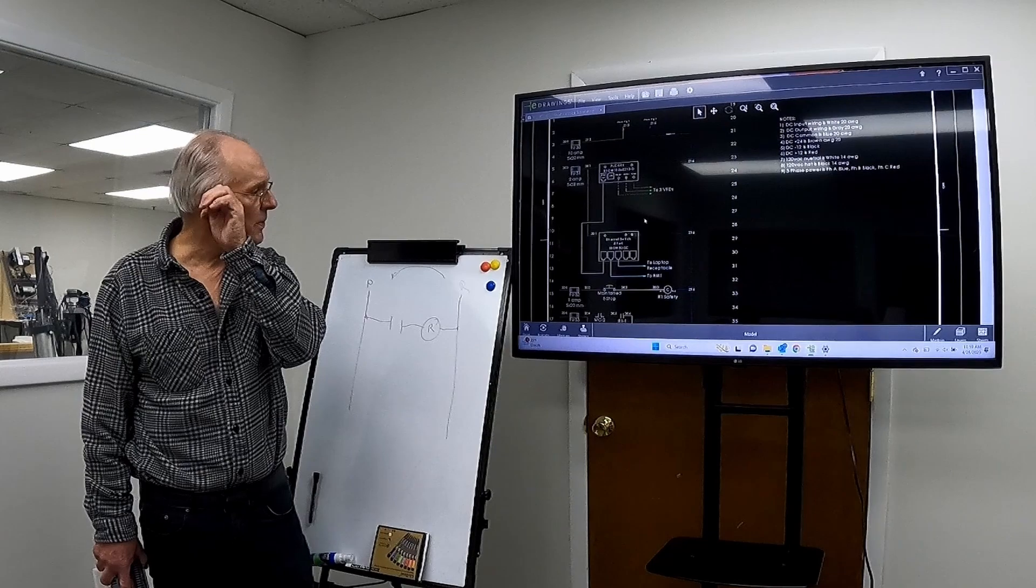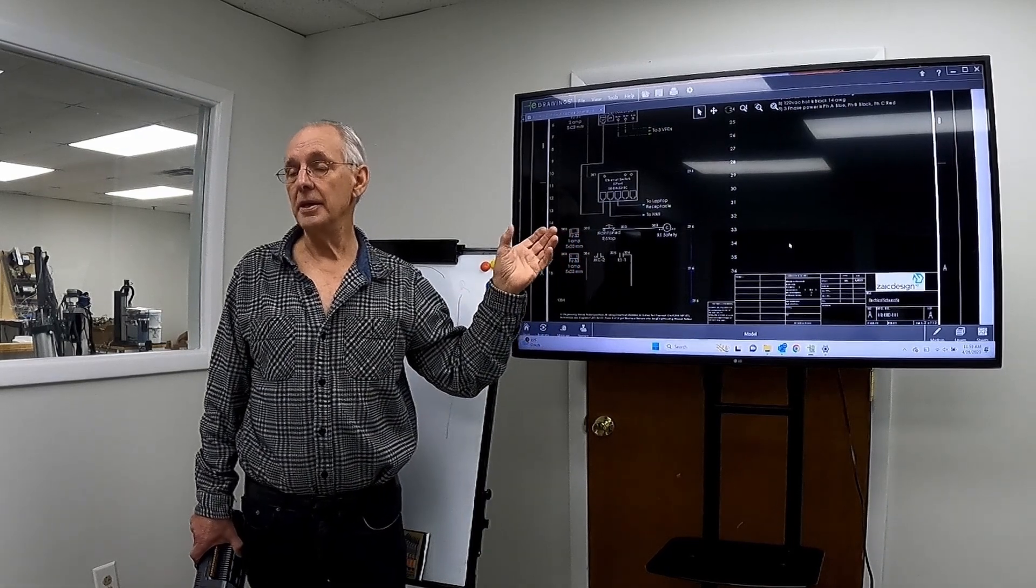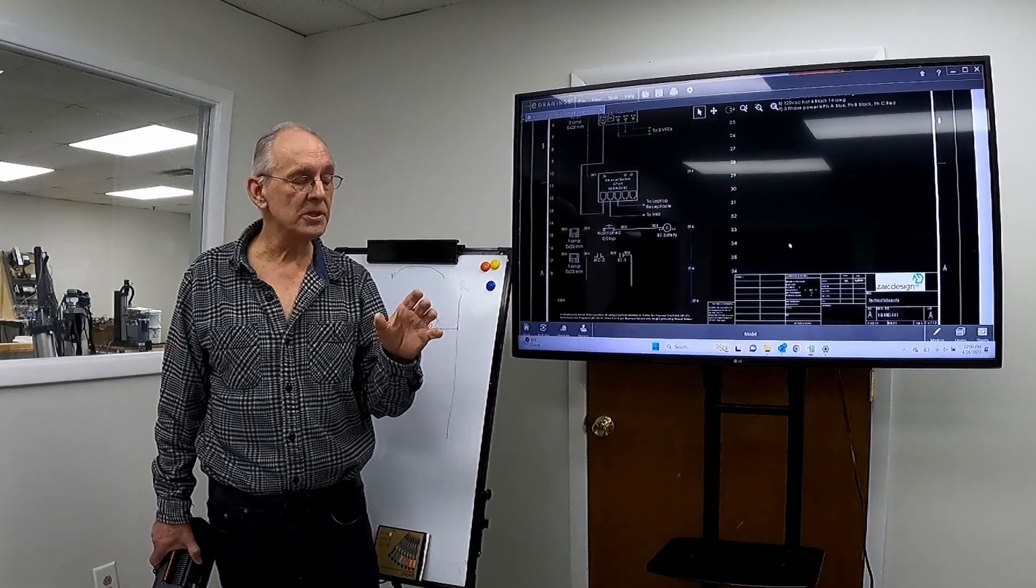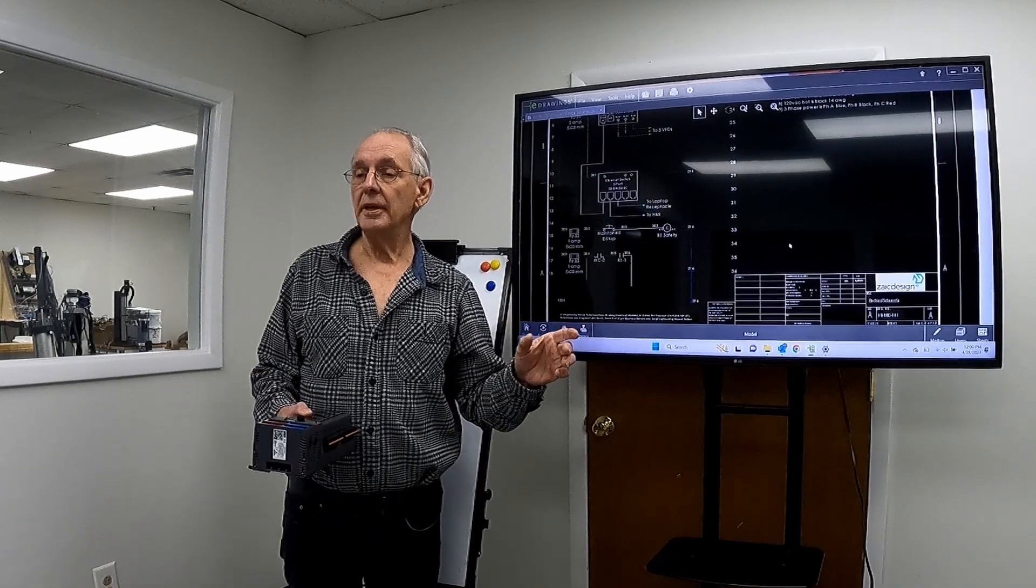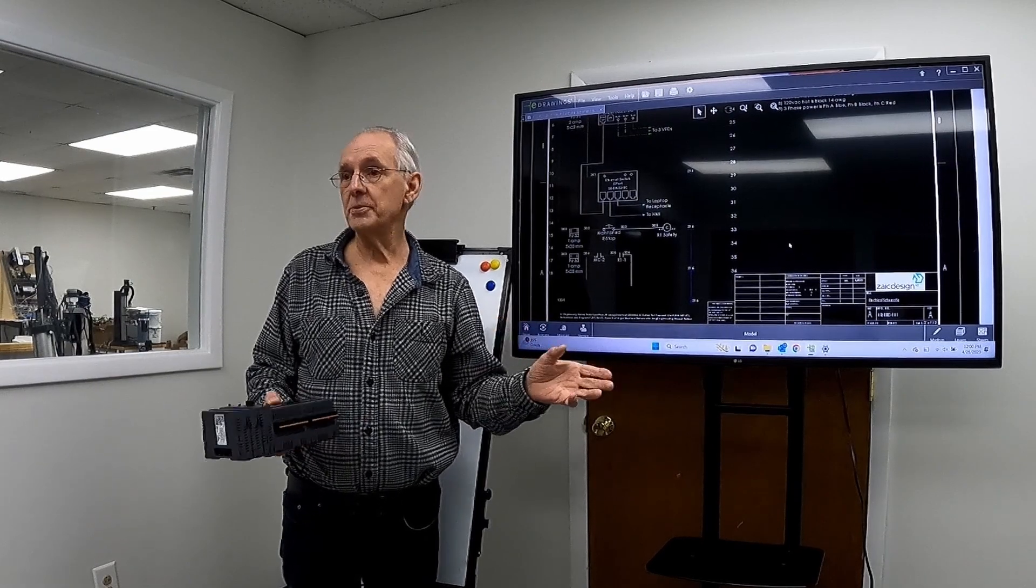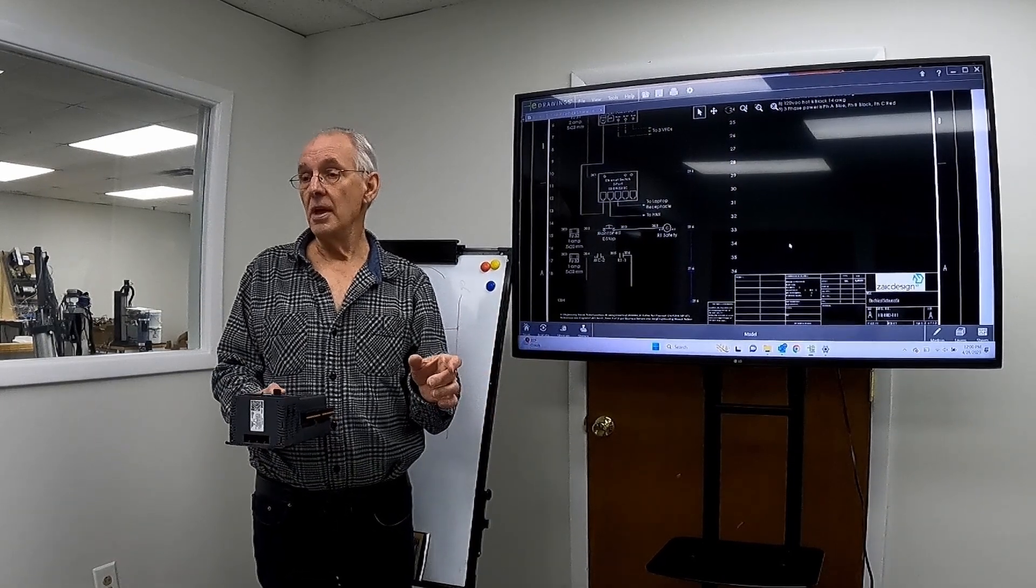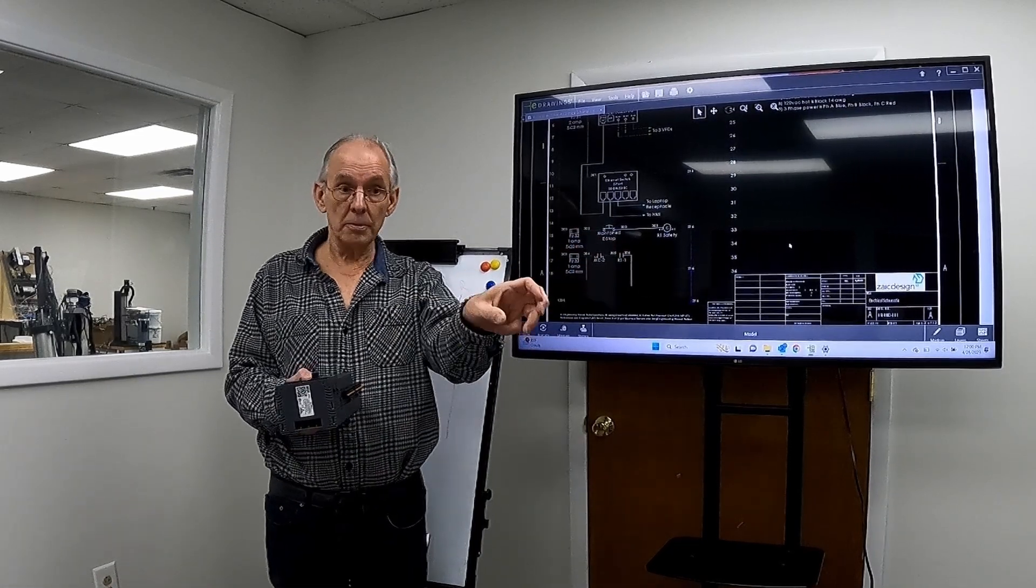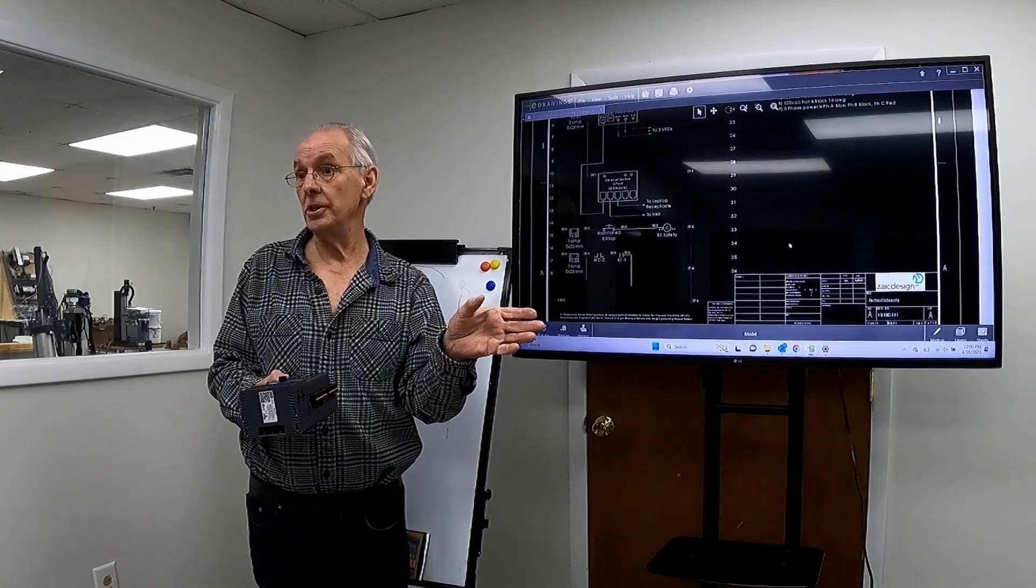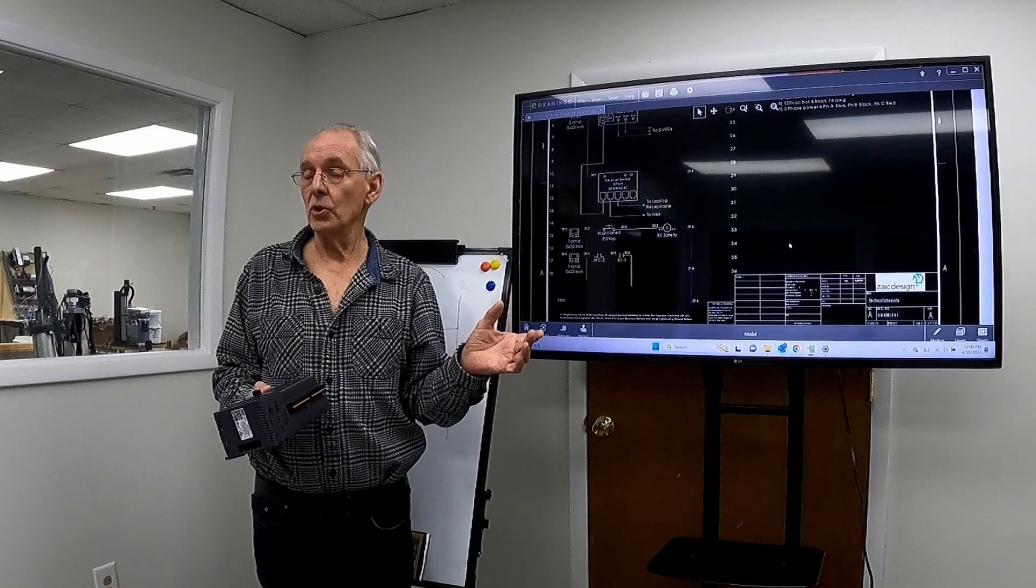Now you'll notice we have a maintained e-stop here. Sometimes you have an electrically held e-stop, and sometimes you have a maintained. What's the difference? Well, in plants where they have machinery that is running and things like your lathe and your mills and stuff, they almost always use electrically held e-stops. There's a power failure, it drops out and nothing restarts. That's really common in industry. However, for a single device like this, the decision of whether to use a maintained - you know, mechanically maintained where you pull the switch out and it's on - is based on do I need to see the thing continue, you know, do I need to know what's going on, or is it okay to hit the e-stop and shut everything off.